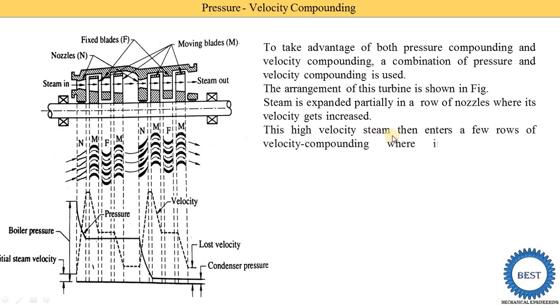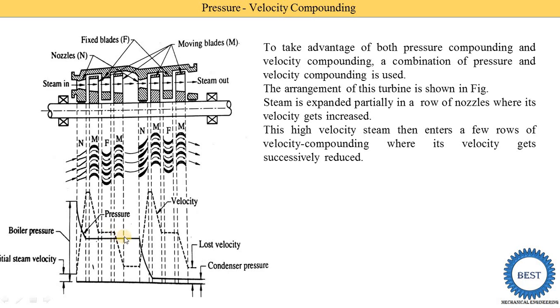This high velocity steam coming out from the nozzle then enters the velocity compounding. Why is it called velocity compounding? Because here fixed blades are used instead of nozzles. If we used nozzles here it would be called pressure compounding. In these moving blades — the velocity compounding — the velocity is successively reduced. Steam coming out from the nozzle with high velocity enters the moving blades where pressure is constant and velocity is reduced. Then it enters the fixed blade where both parameters are unchanged — velocity is as it is, pressure is as it is. Then it enters the second moving blades, where velocity is further reduced and pressure remains constant.